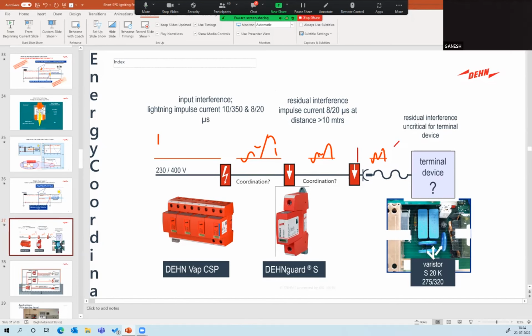will keep on taking the strike. It has a limitation, something around 300 strikes. After that it will fail, and you will get an indication on it. Once you get the indication, you replace it as you would replace an MCB, but it is easier than an MCB to replace. The failure rate of the SPD will be much less than the MCB, and the replacement is much easier.